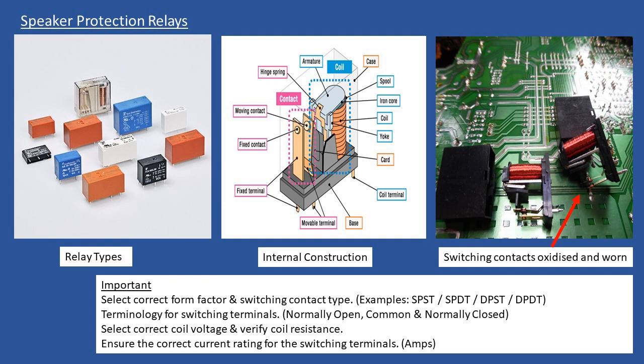In the event of a failure, maybe the amplifier detects an issue, it could be high DC on the output terminals, or a short circuit from the speaker wires or even the speaker coil, the protection circuit will operate and de-energize the relay. Now, when you look at the video, what I've put in there is an overview of what this speaker protection relay looks like. I refer to something called form factors, and what that means is that each type of relay has a particular design.